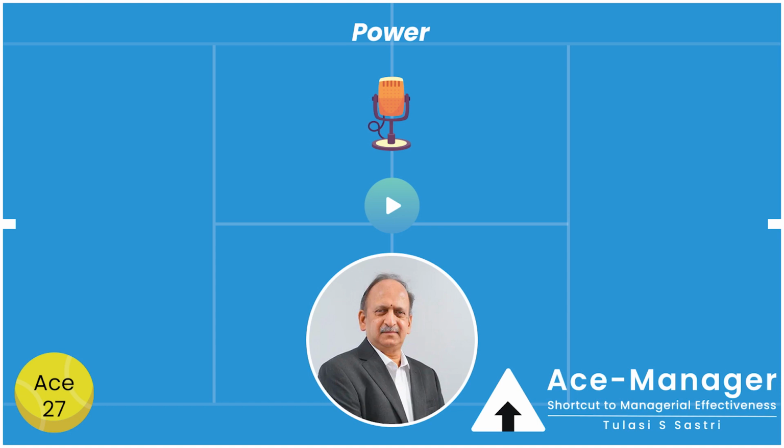Those days, diesel used to cost 3 rupees 80 paisa per liter. Each of the small 250 kVA gensets were giving a yield of 1 unit of power per liter of diesel consumed. This meant effective cost per unit using the small gensets was rupees 3.80.